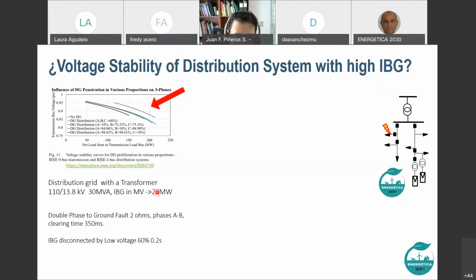Then we apply a double phase to ground fault here, with 2 ohms. Something normal could happen, and we clear this fault in 350 milliseconds. Because of the recommendations about, for example, low voltage tripping, to avoid non-conventional generation staying connected, we have a tripping time at 60% voltage, 200 milliseconds.